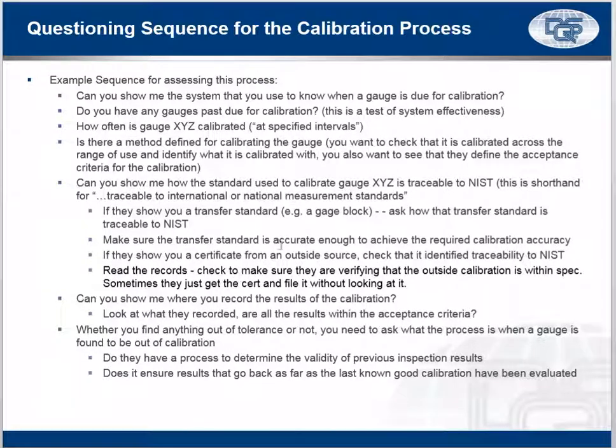You also want to make sure your standard is accurate enough to achieve the required calibration accuracy. So this happens a lot of times when the transfer standard is not a gauge block. So let's say I have go, no-go pins. And they'll say, well, we calibrate these pins, which are usually good to 3 decimal places, with a caliper, which is usually accurate to 2 or 3 decimal places. Really, to get that 4 times to 10 times accuracy, they should do it with a micrometer. Can you show me the records?